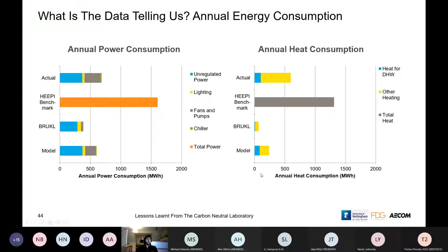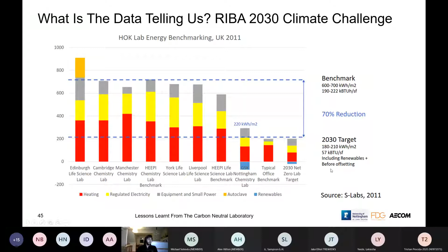In terms of the RIBA 2030 climate challenge, using the data referred to earlier, even though we're not getting anywhere near the model, we're doing very well compared to what RIBA have identified a laboratory building should achieve. RIBA reckon that by 2030 we should be achieving about 200 kilowatt hours per meter squared for a laboratory building, and we are at about 300 kilowatt hours per meter squared without renewables, 220 with. So actually we are not that far off, and we've estimated that if we can sort out the controls issues we have, we can hit that 2030 target about 9 years before it's due.